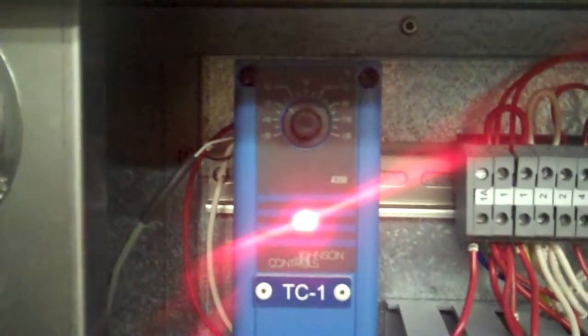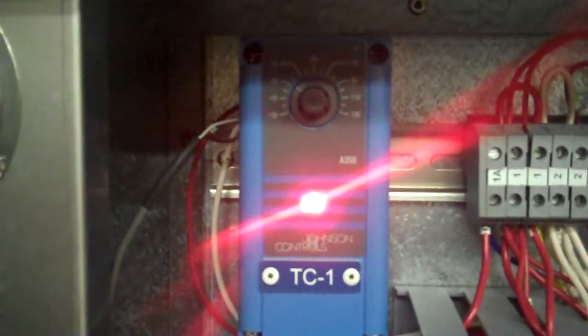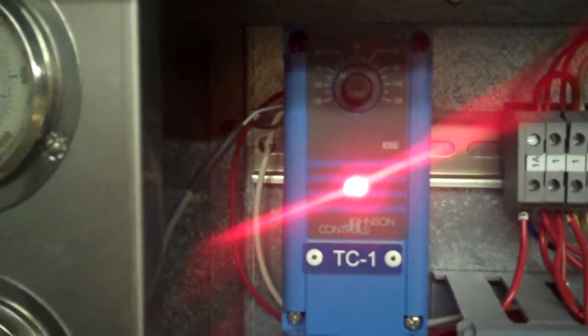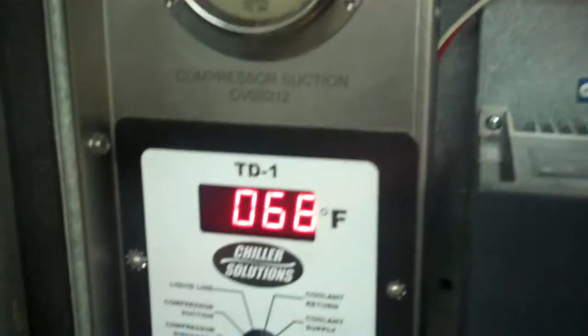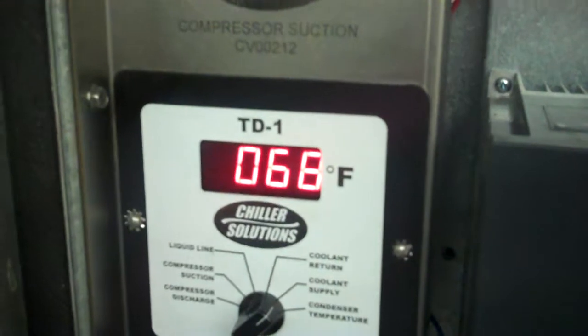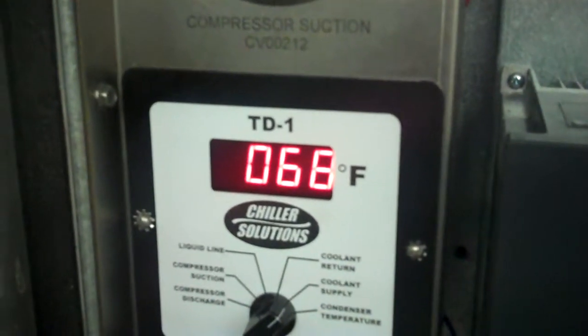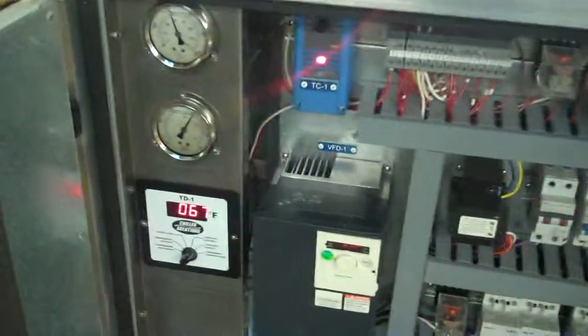We have a 30% glycol mixture running through a loop in the unit right now. We heated it up with ambient and this coil system that we have right here. And we got a little space heater on it. We just heat it up to about 70 degrees or so, and that actually gives a little bit of a load, so we've been cycling this on and off all day.